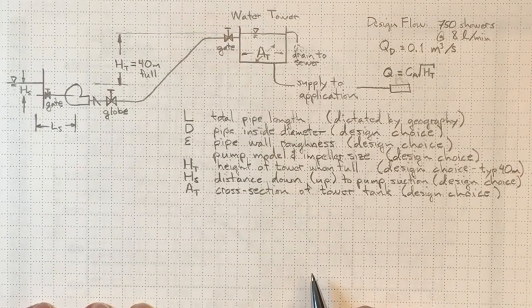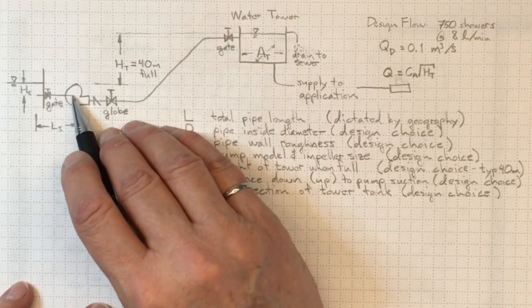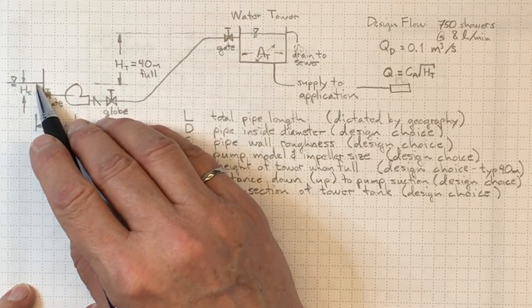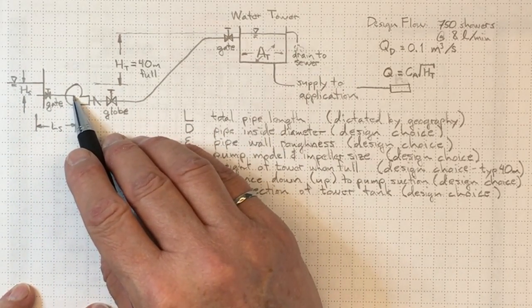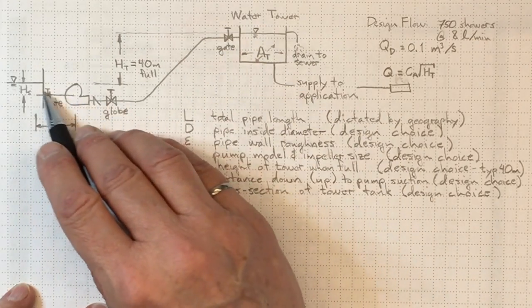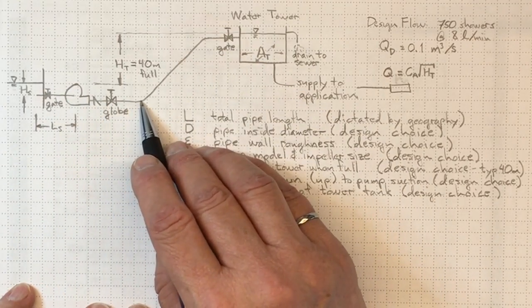Let's look back at the diagram for our practical system. Here's our pump. We've already put it a little bit of a distance below the surface of the water to improve the NPSH system. We've reduced the losses in our piping system by going to 8-inch pipe instead of 6-inch pipe. And that seems to make sense for us.